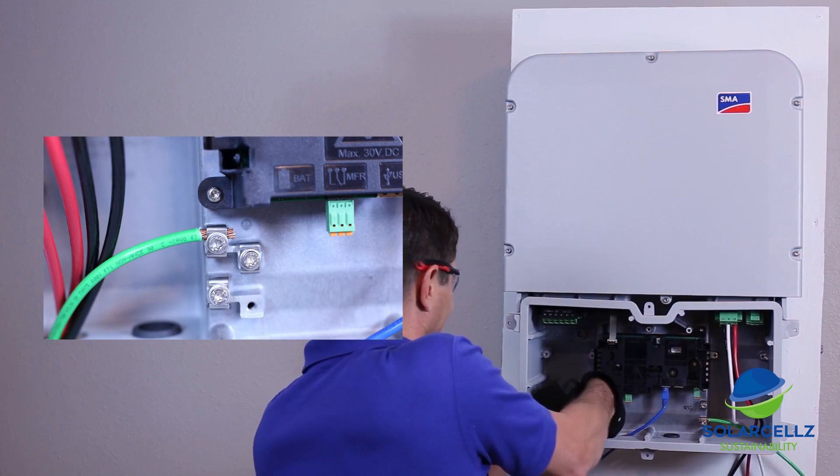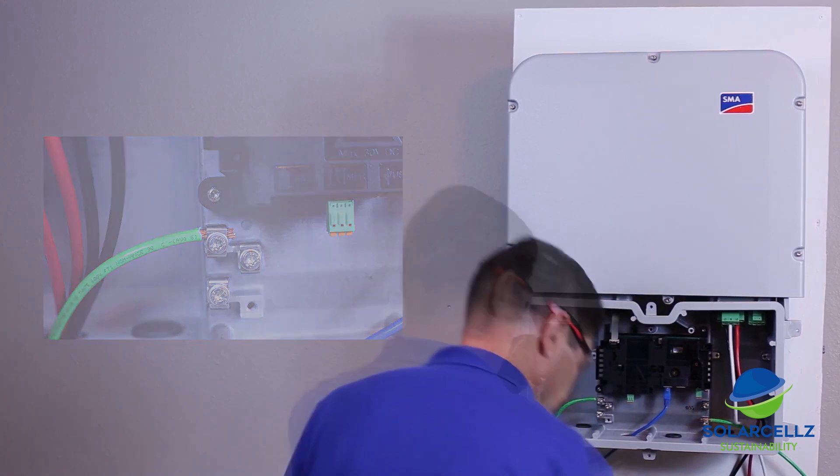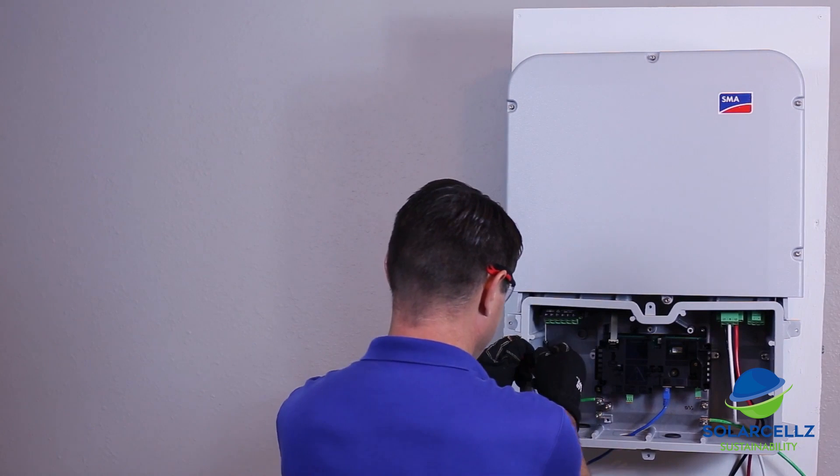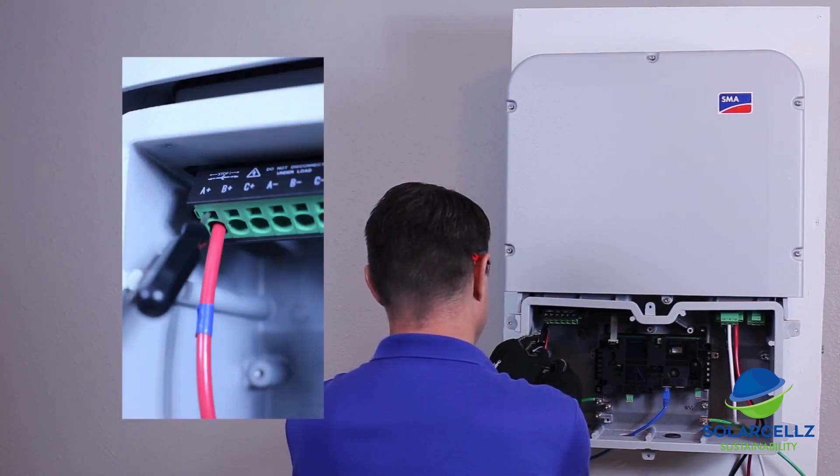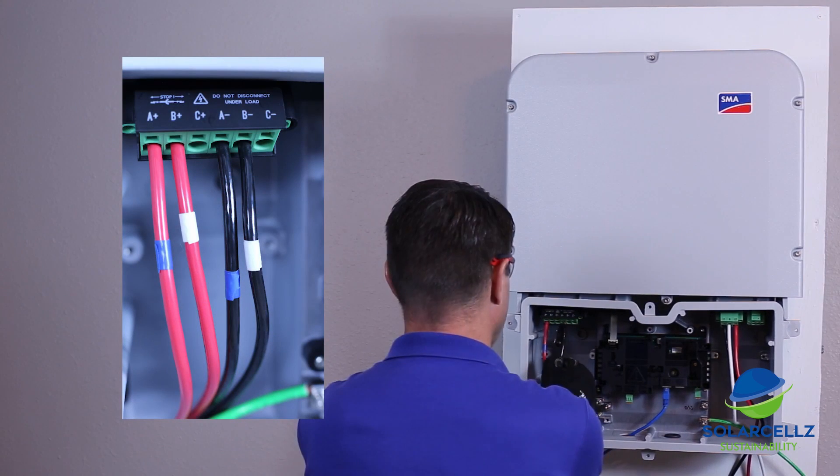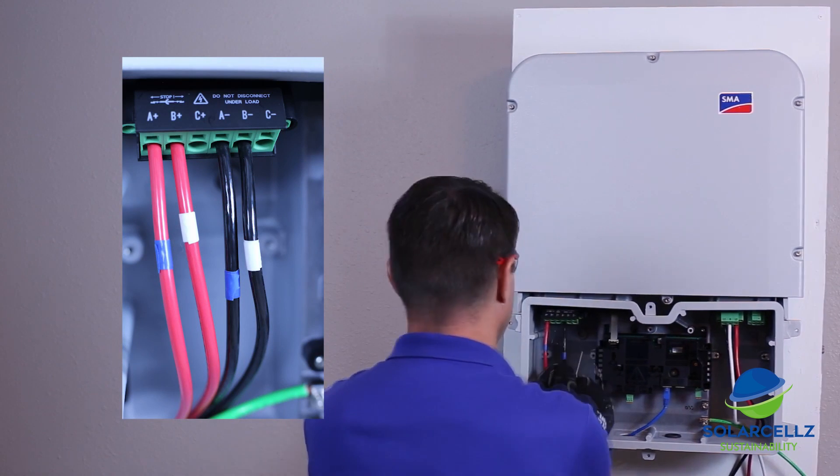Attach the DC ground conductors in the appropriate positions, ensuring the conductor is seated between the clamp and the washer and tight. Insert the DC positive and negative conductors for each string into the appropriate positions on the DC plug. Ensure each conductor polarity is correct and the string conductor pairings are correct.